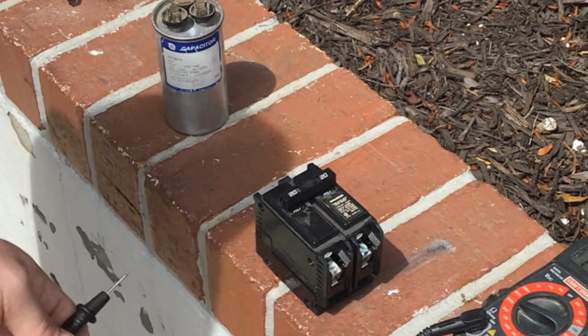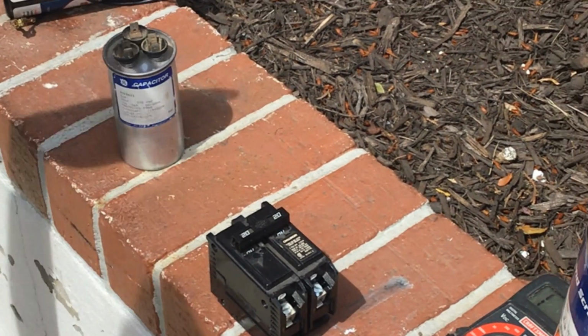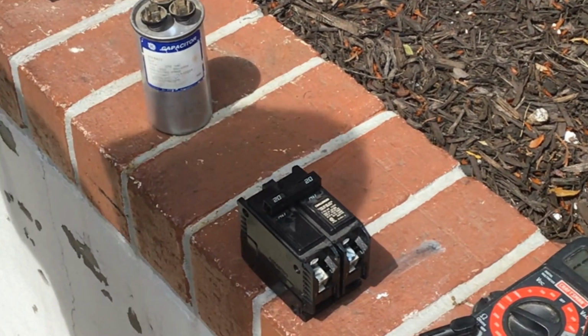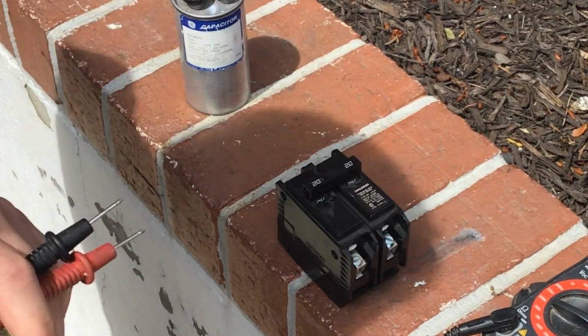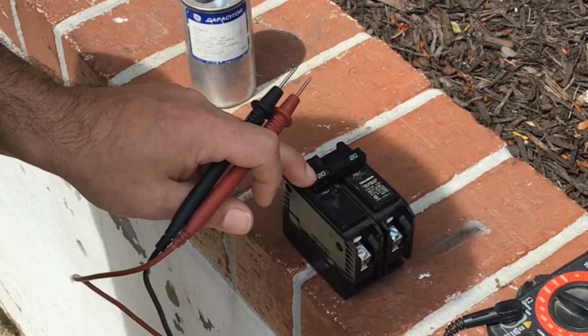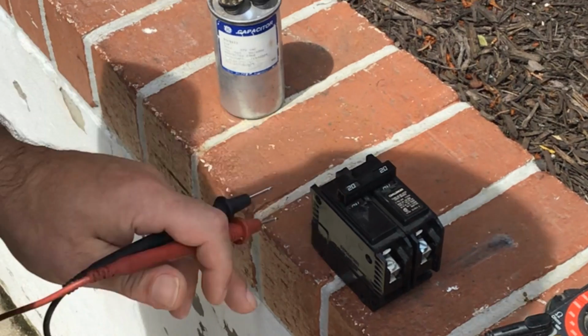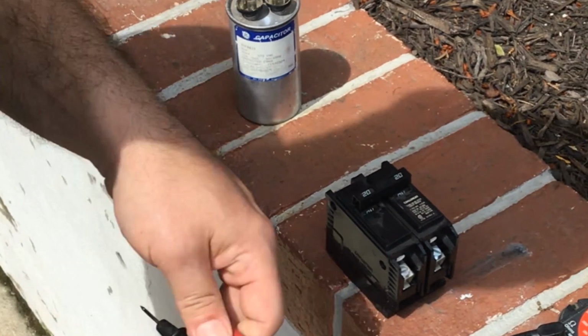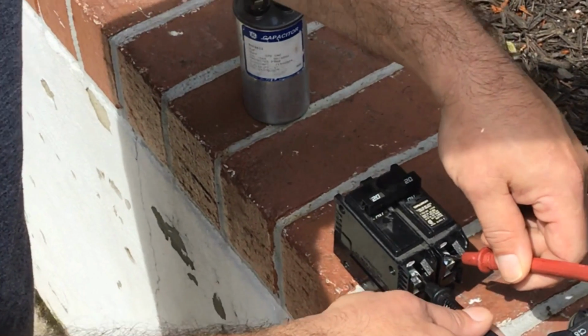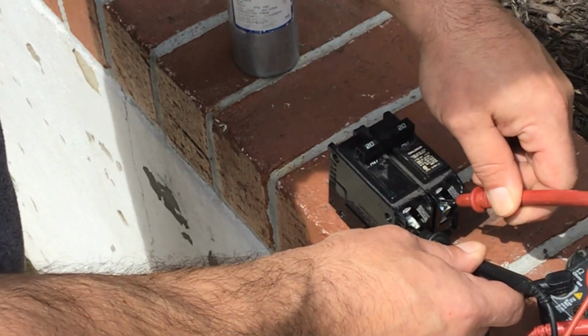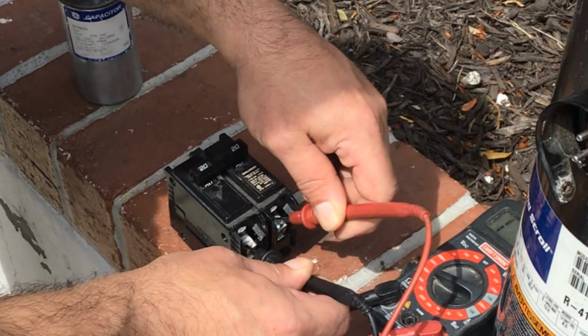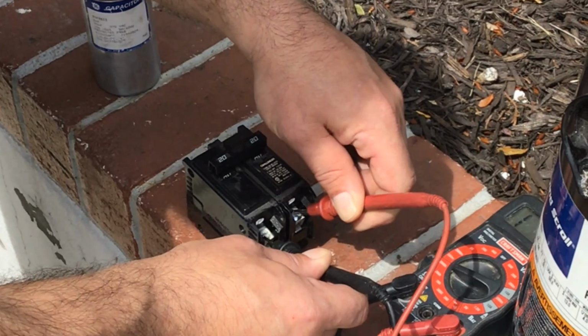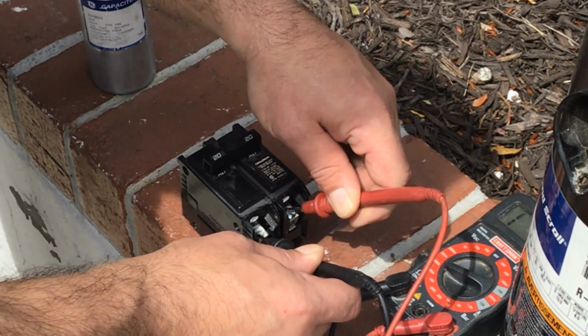This is a circuit breaker pulled out of the panel. Your outdoor condenser is always going to be on a double pole breaker. If this happens to be a 20 amp, it's usually going to be on a 30 amp. All you would do is test both your output wires for 240. And if you're only getting half, or you're not getting anything and your breaker's on, replace your breaker.